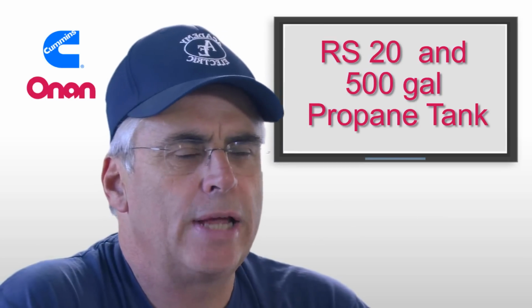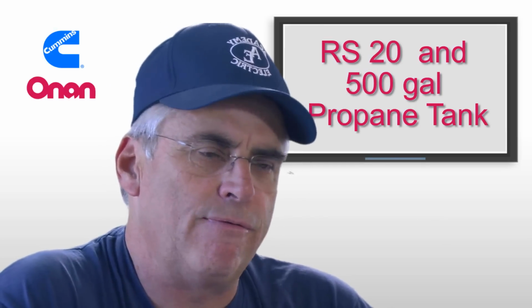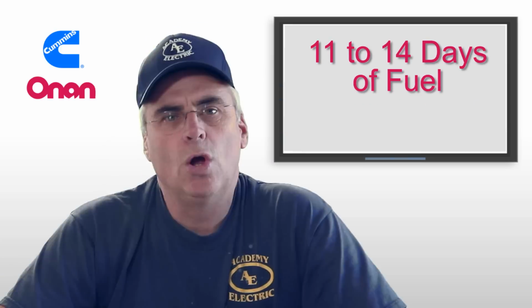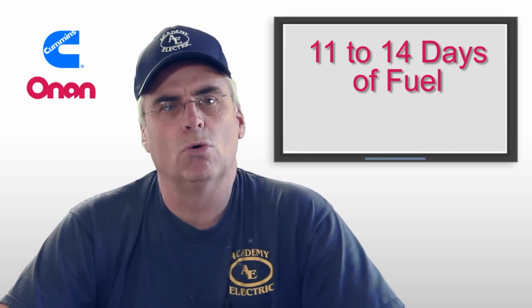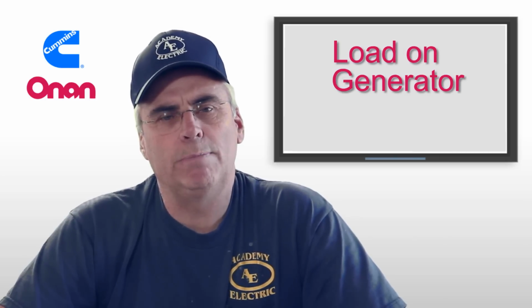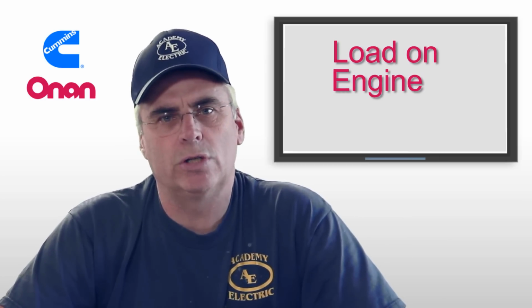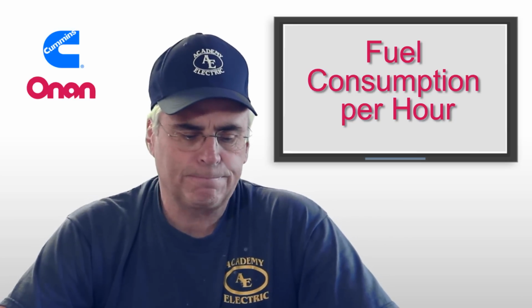In fact, post-Sandy, some of our customers with the RS-20 generators and that 500-gallon tank buried in the ground went 11 and even up to 14 days of fuel due to the load on the engine. Load on the generator is directly proportional to load on the engine, which is directly proportional to how much fuel you're going to burn an hour.